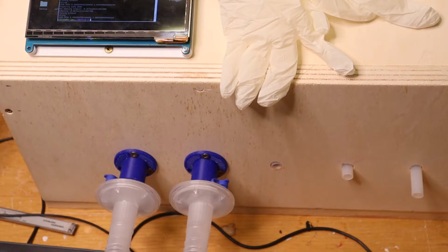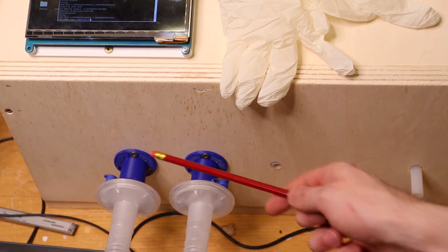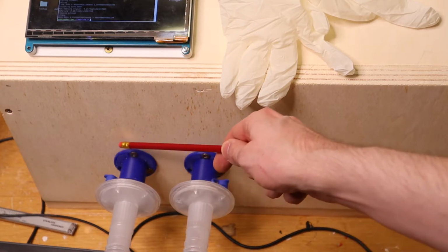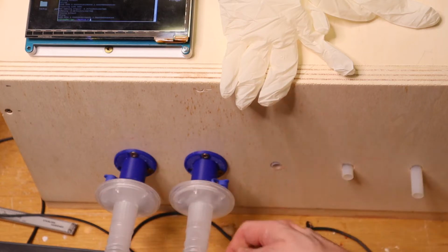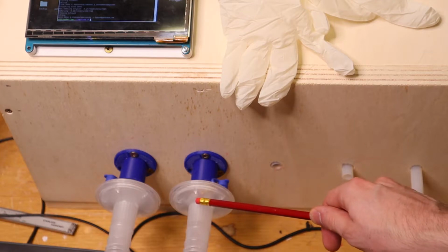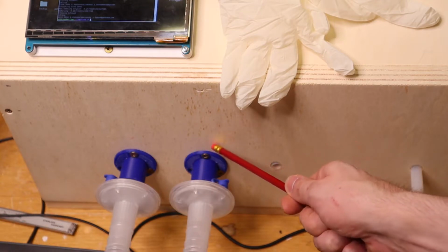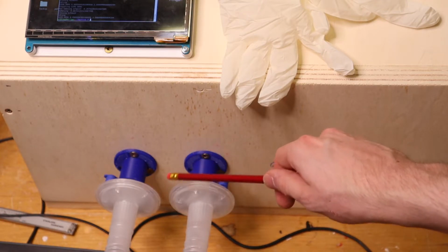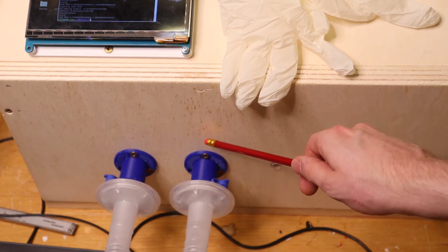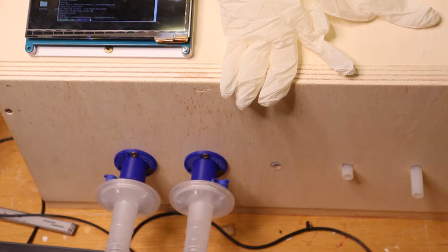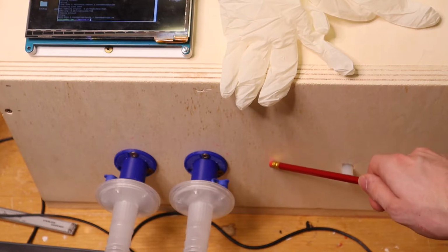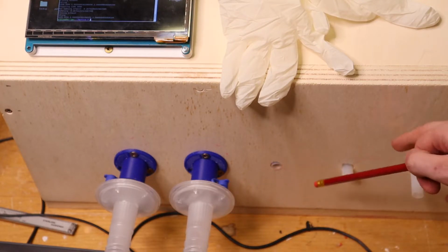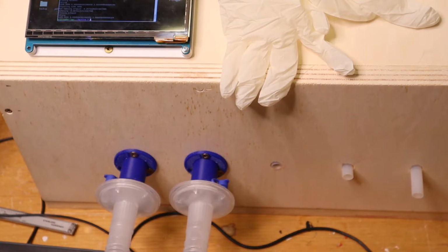Looking a little bit further down, we have the gas inputs and outputs. So from left to right, we have the gas coming out of the machine and going into the patient. To the right of that, we have the air returning from the patient going back into the device. And this is necessary so that the ventilator can control when the patient is allowed to exhale. Here we have a small little exit for the air from the patient to finally leave the system.